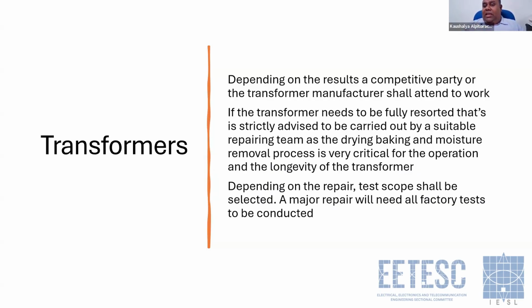If the transformer needs to be fully restored, it is strictly advised to be carried out by a suitable repairing team, as the drying, baking, and moisture removal process is very critical for the operation and the longevity of the transformer. I have seen many events where these transformers were rewound by third parties, and they were blown at the instant they were energized. So make sure that does not happen, because that makes you order another transformer again. So don't let that happen. Find a suitable party.